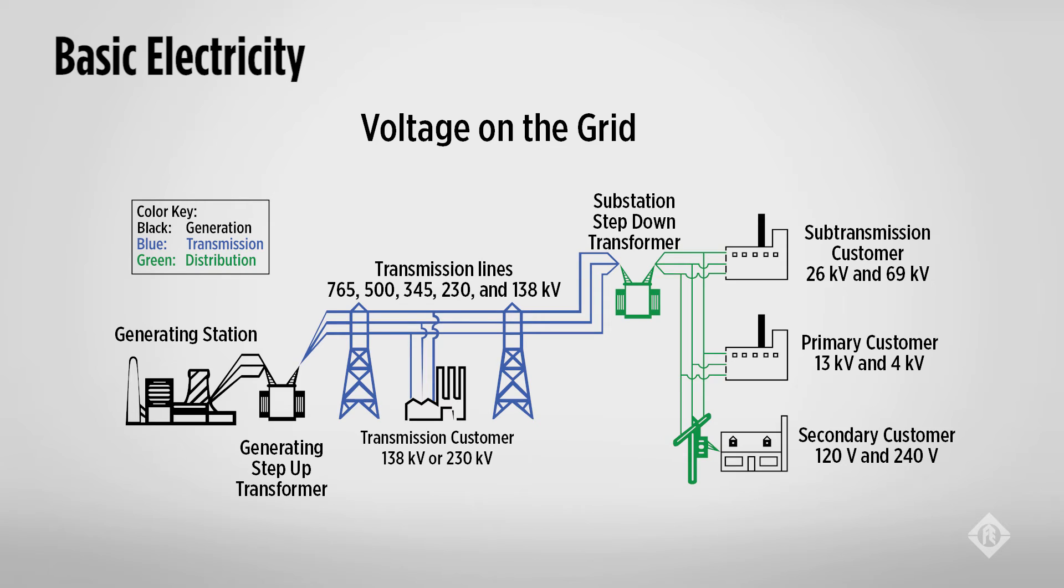Voltage is the amplitude of the electricity measured in volts. Most voltage at the site in North America will be around the following values: 120, 240, 480, and 600. The higher the voltage, the less copper wire needed to supply the same amount of power to the load. Power loss in the wire is dependent on the voltage and wire size, which is resistance that the current will see. This is why the power lines going throughout the country are high voltage, sometimes as high as 765,000 volts.